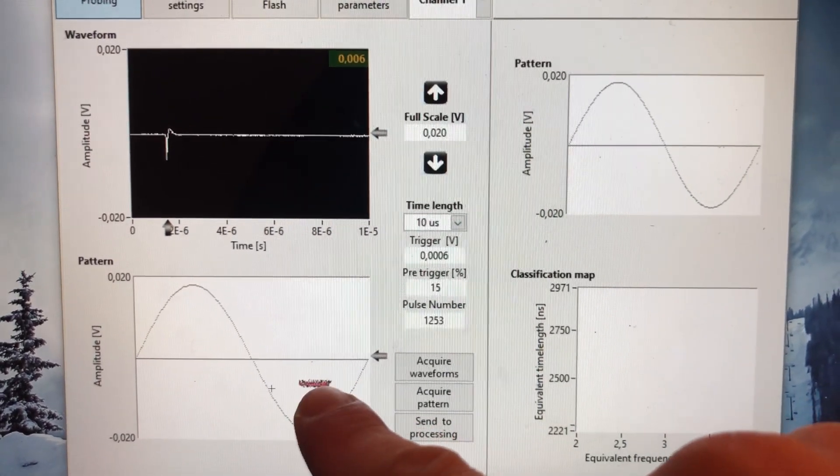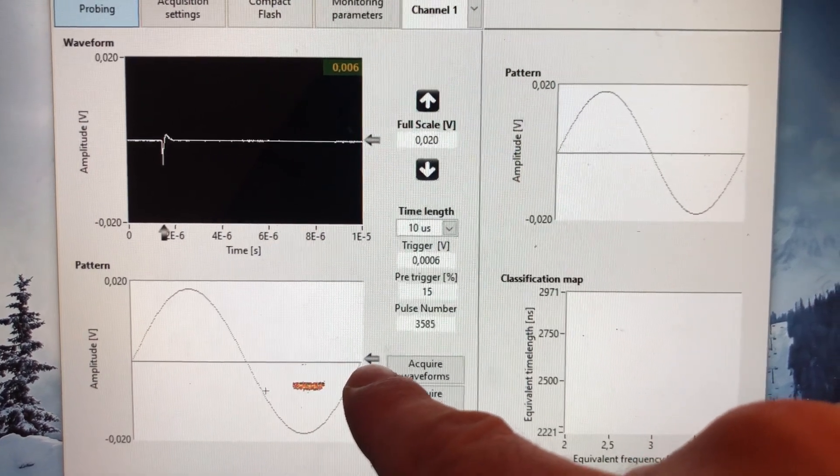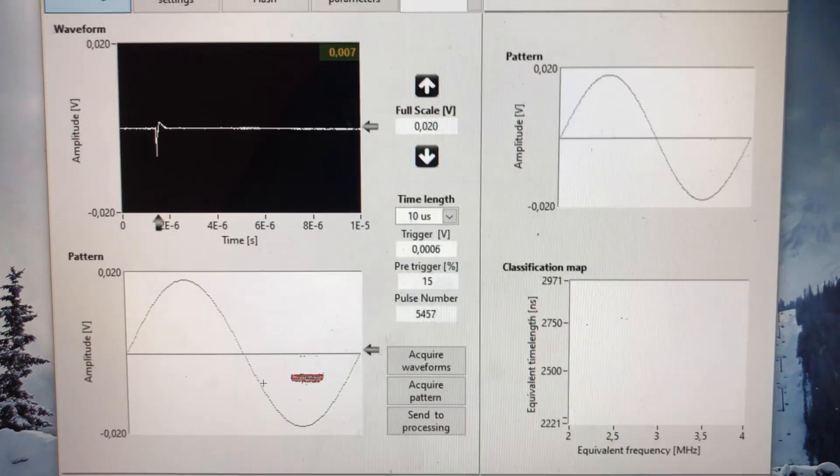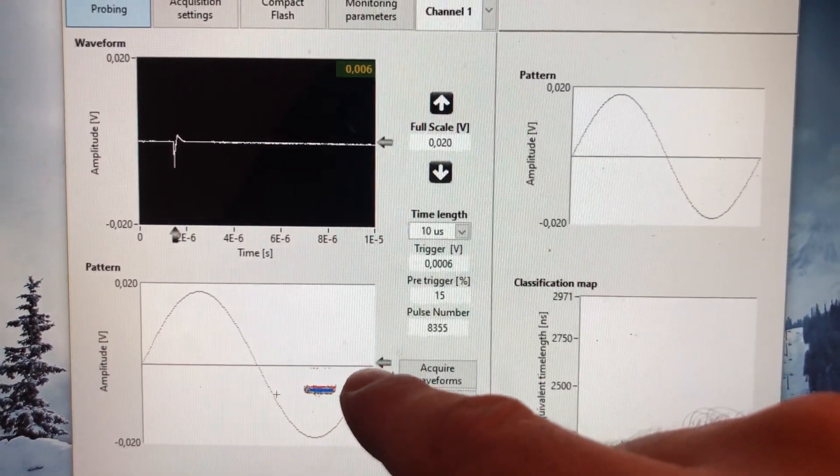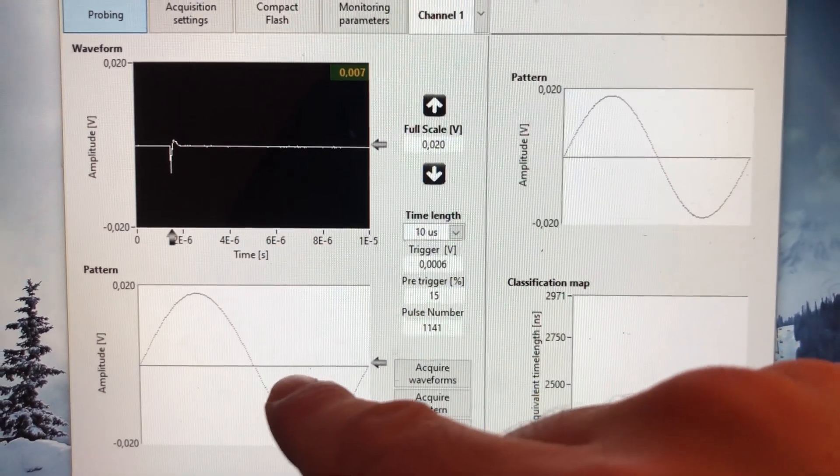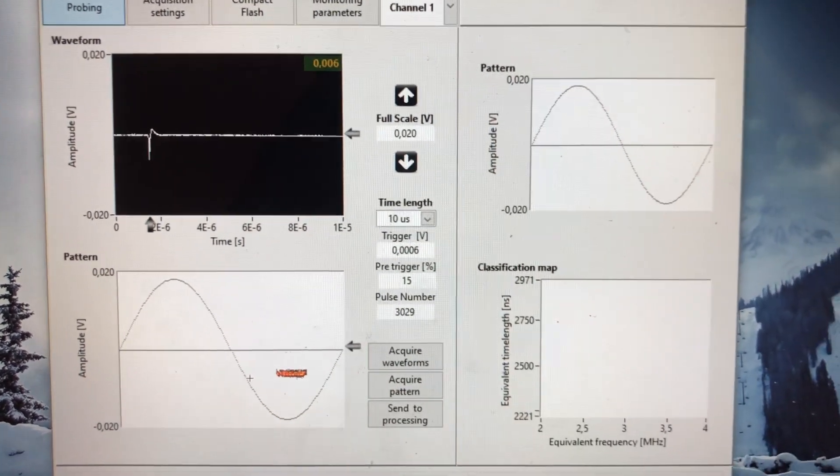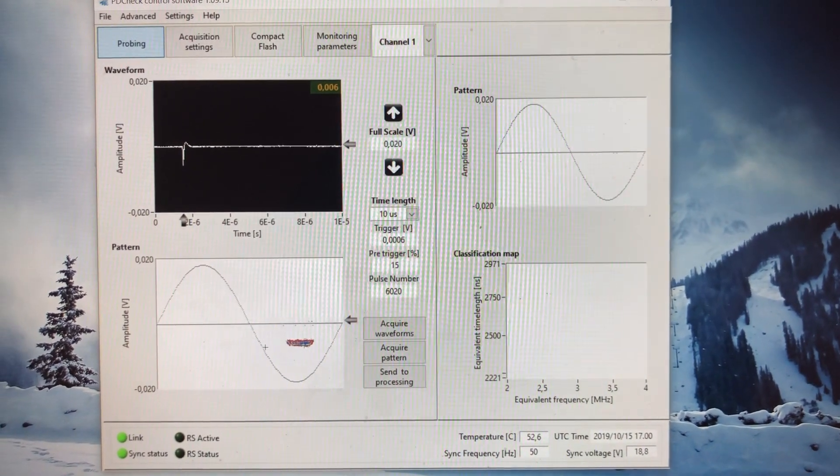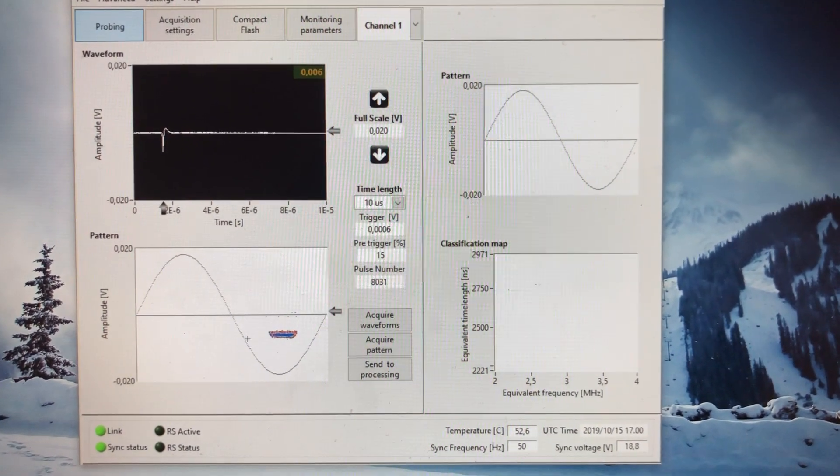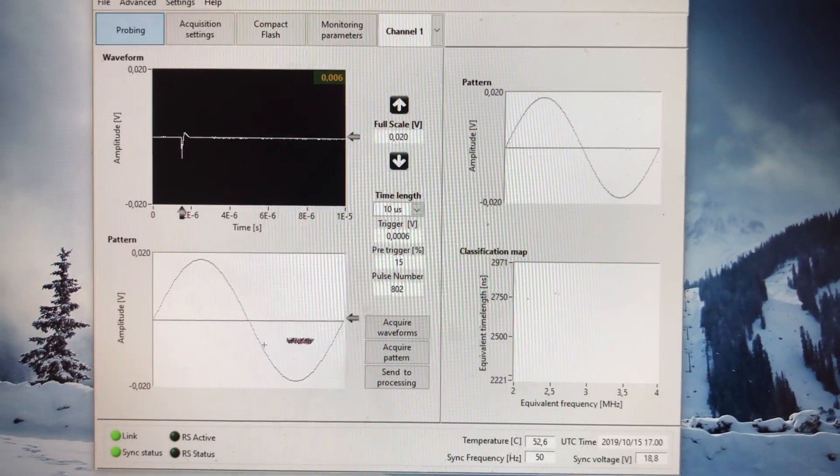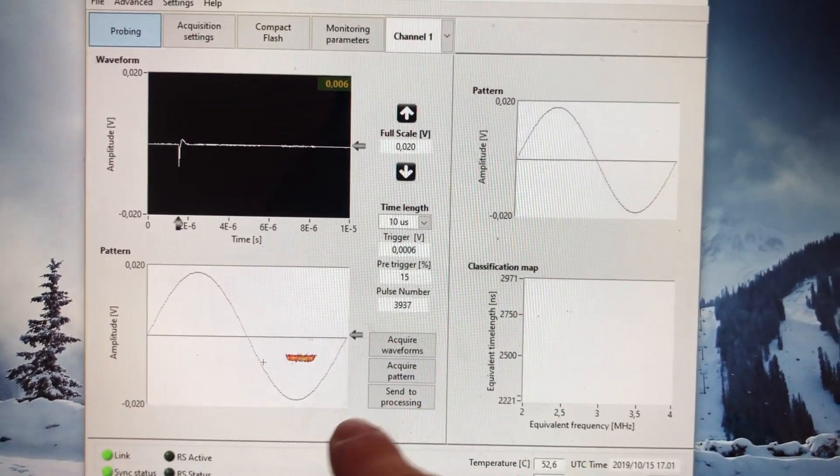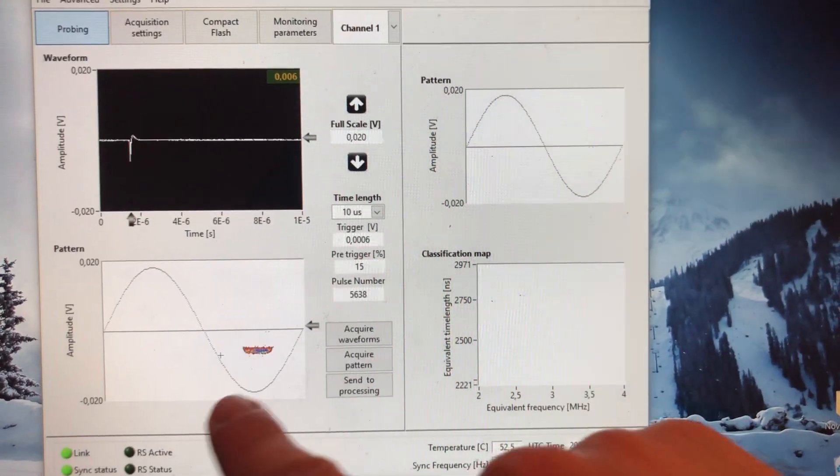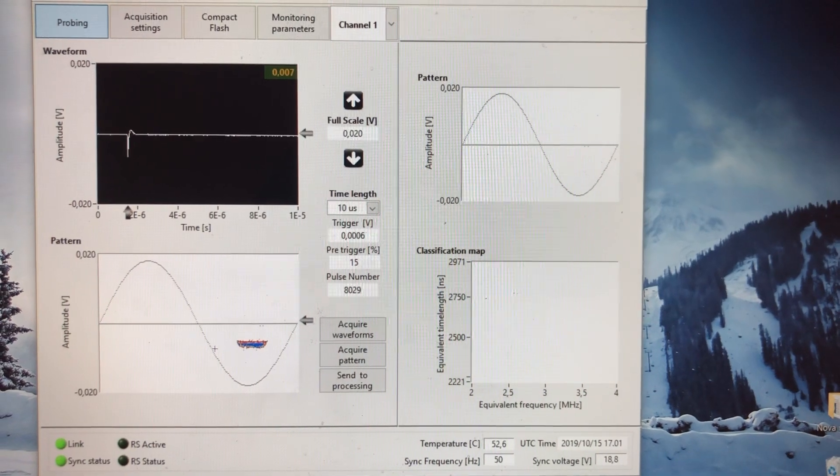Another very important thing when defining Corona: it's always not stuck to the X axis or to the trigger level. Surface PD, for example, would be stuck to a trigger level. But here we have some energy, some space between the trigger level, which is very close to X axis, and the Corona which is happening. This is how we can use TF map to filter. And I hope today you learned what Corona looks like, what the PRPD phase resolved PD pattern, which is this of Corona, how is it represented in the PRPD. Thank you very much for your attention. I'll see you in the next video.